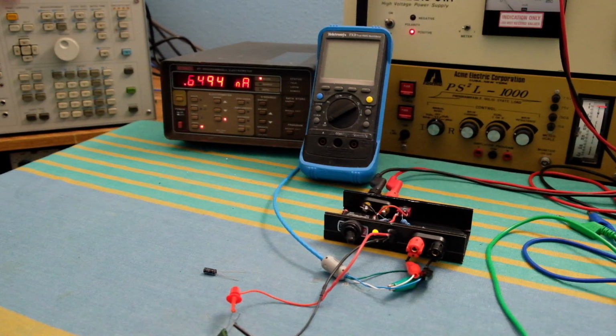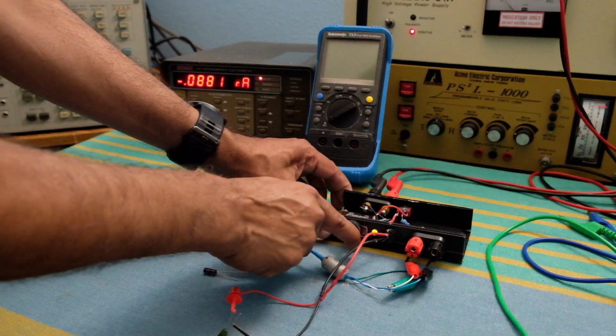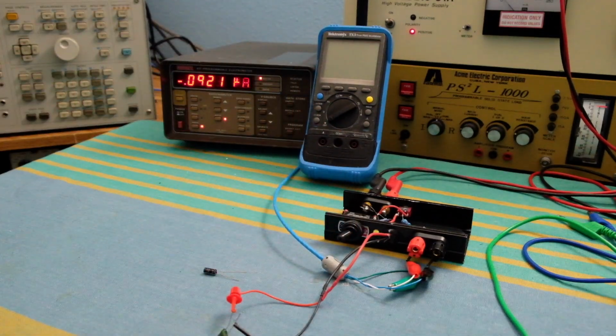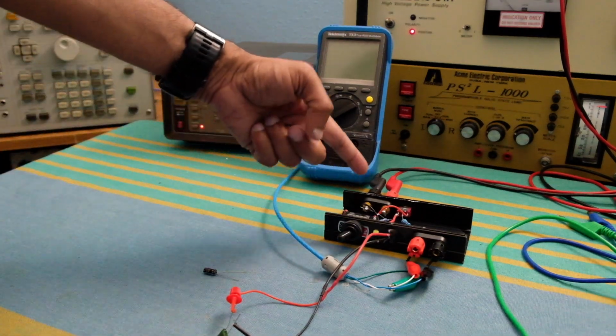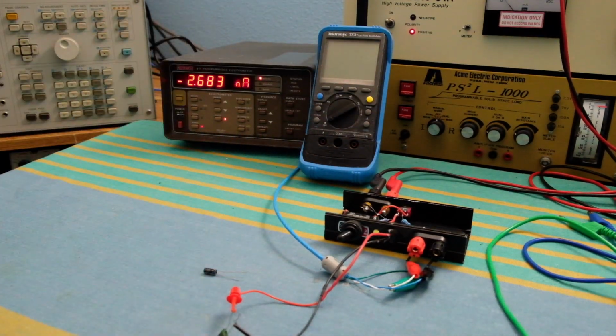So that's the good thing about these electrometers, which have very, very low current measuring capabilities. But you also have to deal with noise, as you can see at these low current values. So again, if I turn this off, it pretty quickly discharges itself because of that. The LED circuit itself is enough to quickly discharge it out.